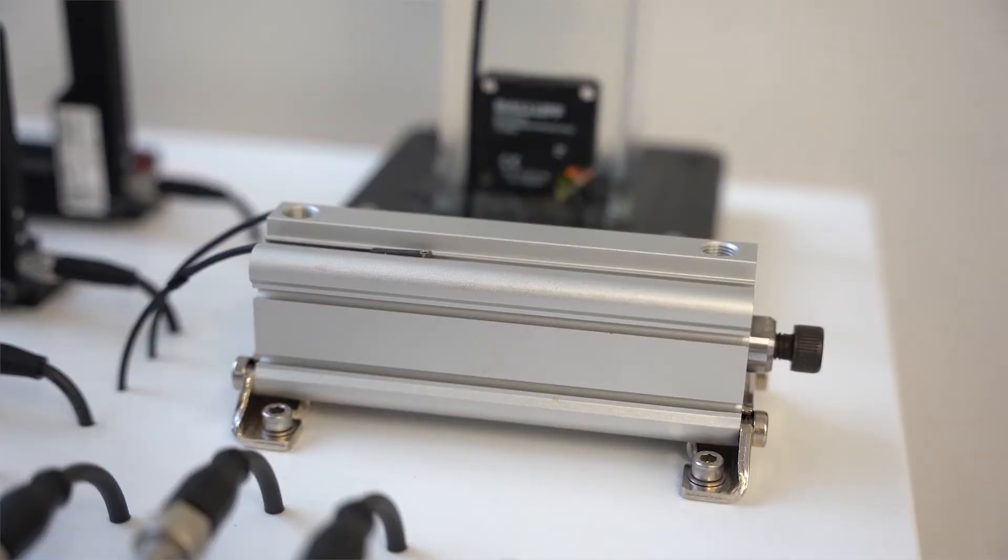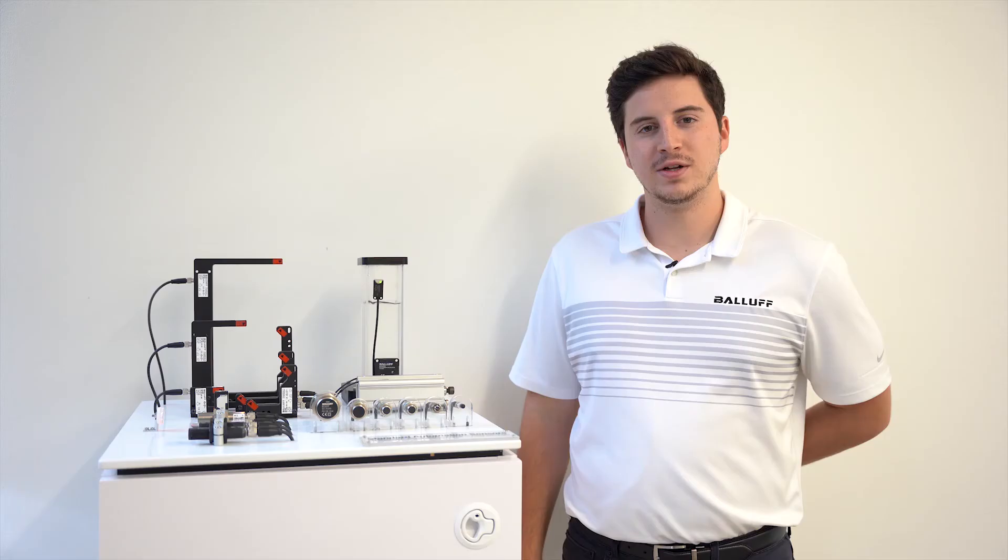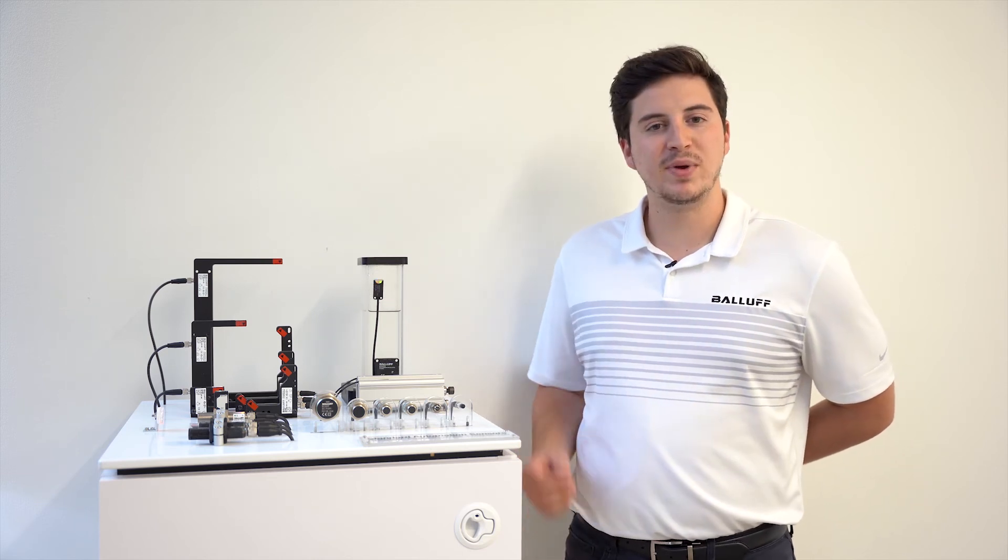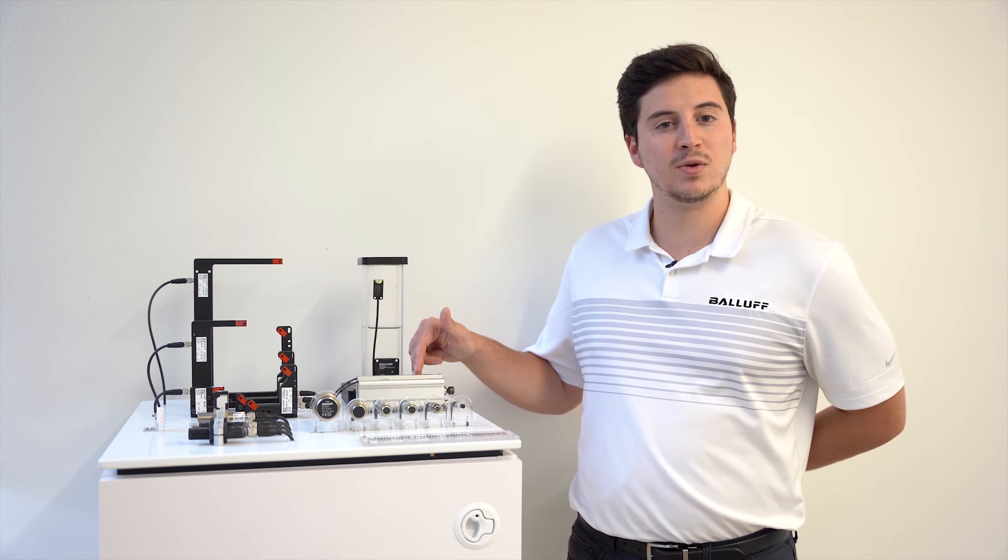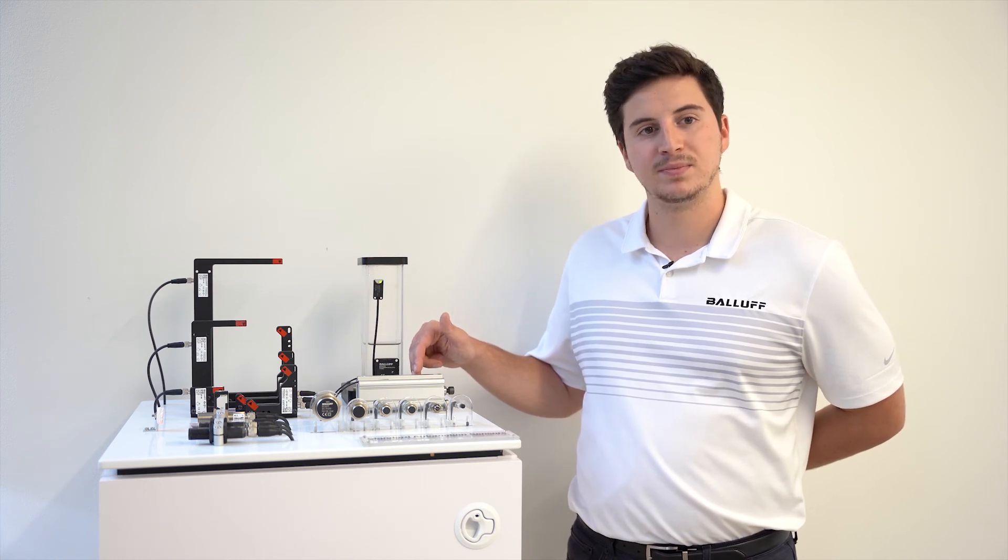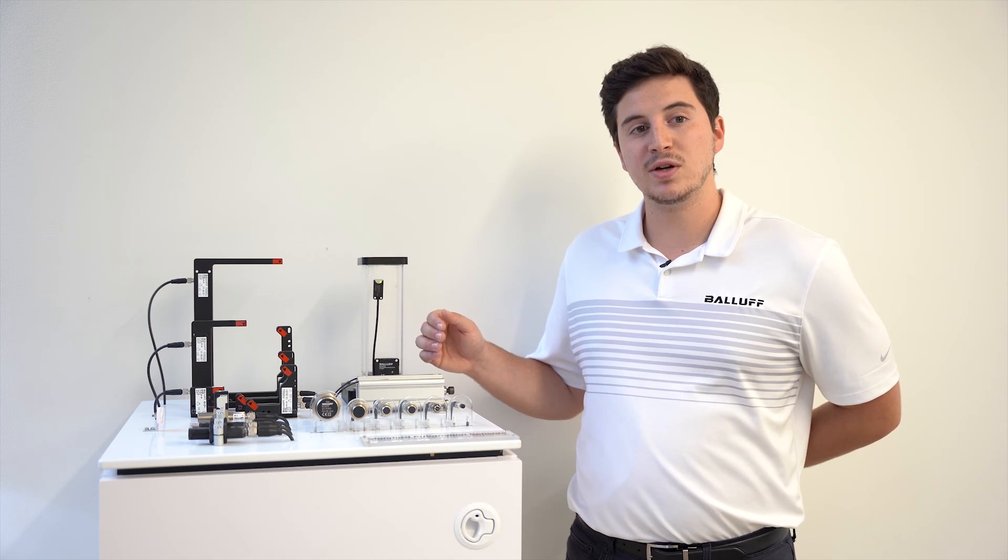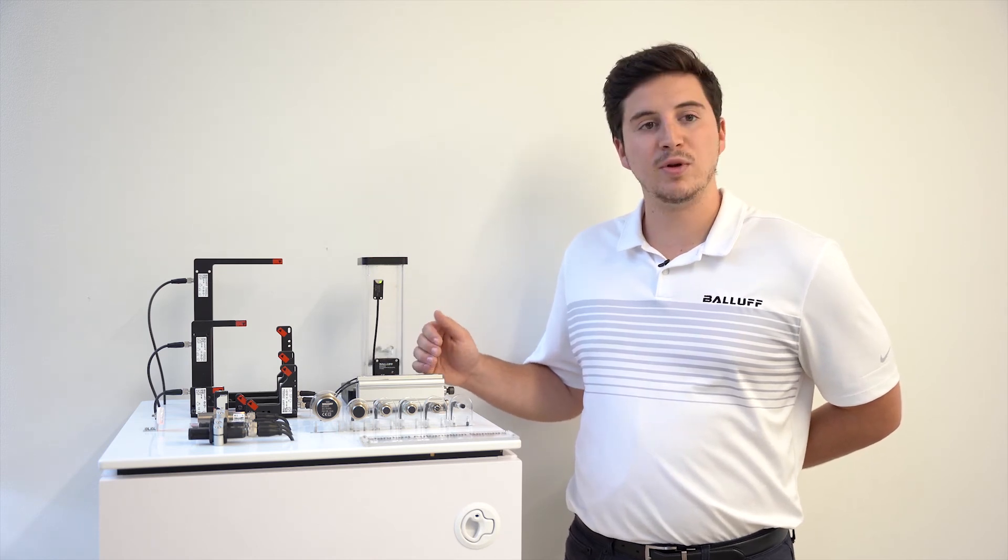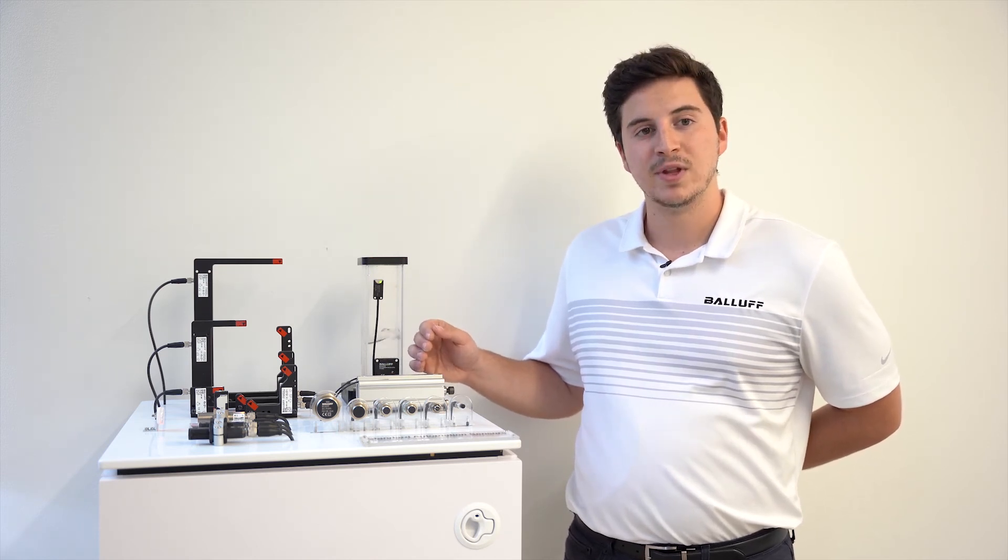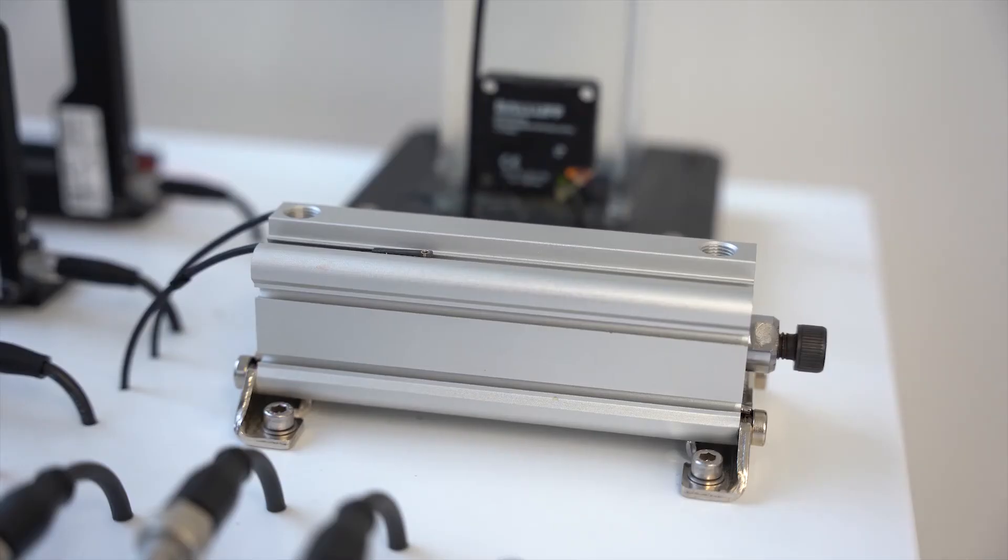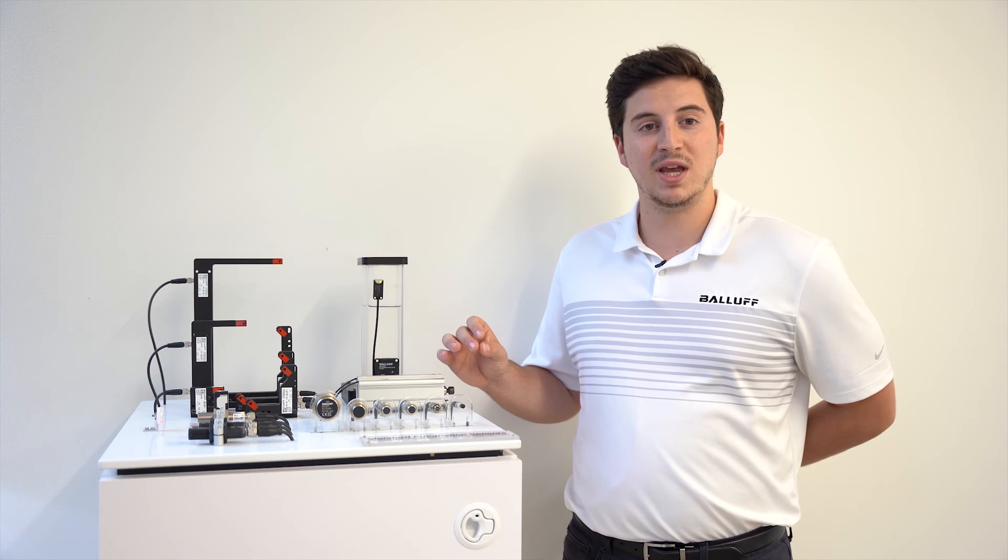Shown here is a short-stroke cylinder demoing Balluff's magnetic field sensor. Magnetic field sensors detect piston position through the cylinder wall of a pneumatic cylinder. These magnetic field sensors are designed for a C-slot cylinder, but they're also available in T-slot form factors. What's great about them is they mount flush with the cylinder, making them great for space-critical applications.